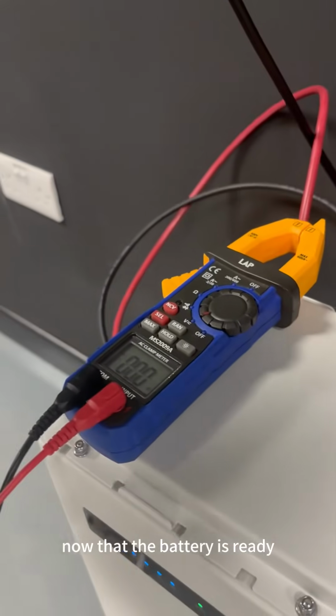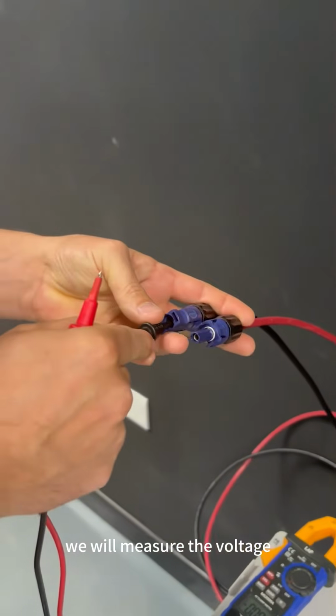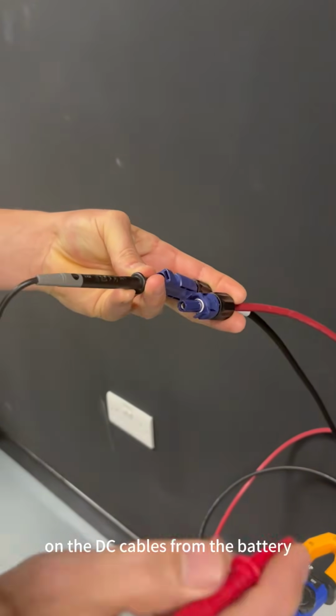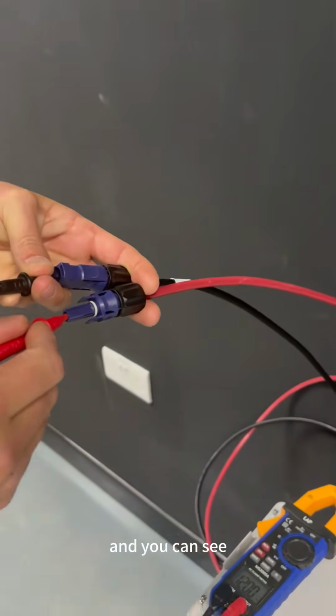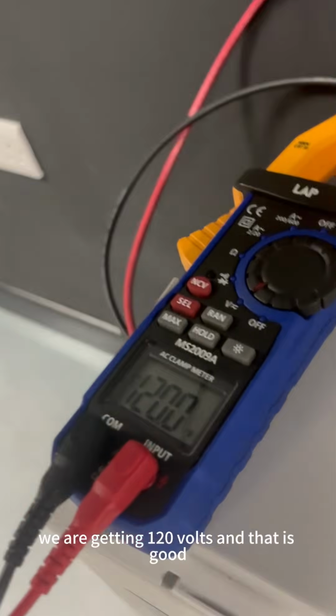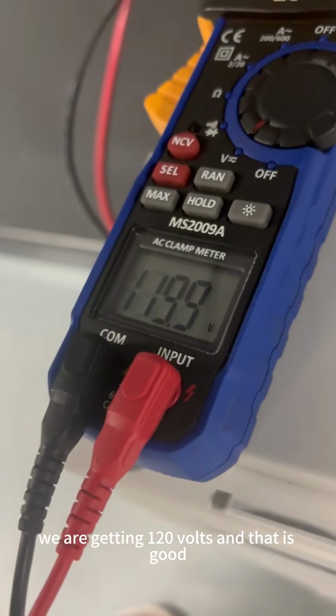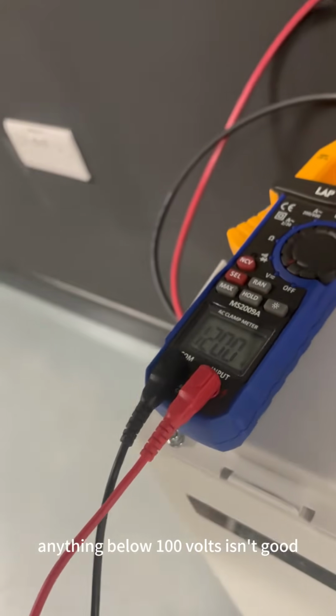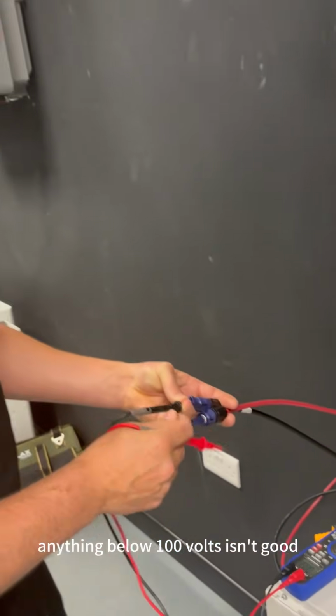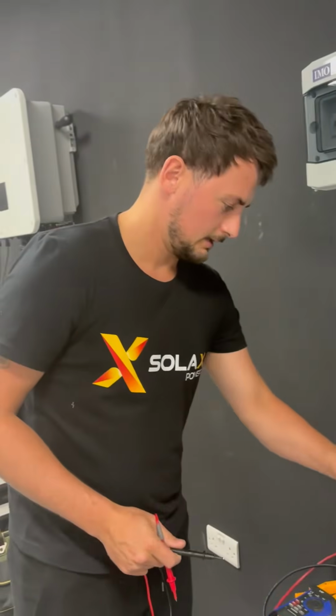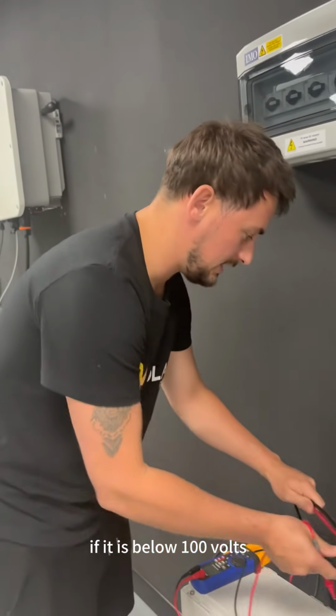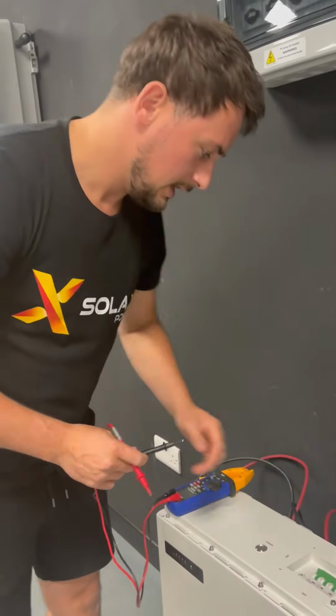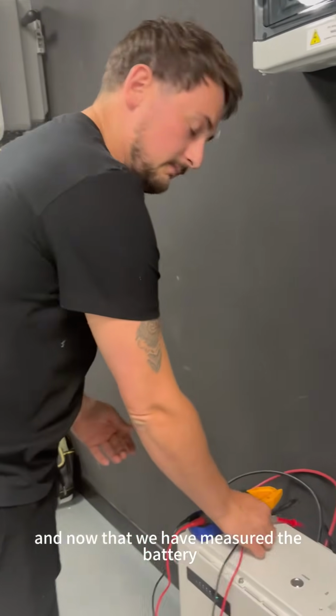Now that the battery is ready, we will measure the voltage on the DC cables from the battery. And you can see we are getting 120 volts, and that is good. Anything below 100 volts isn't good. And please take a picture of that if it is below 100 volts. And now that we have measured the master battery, that is okay.